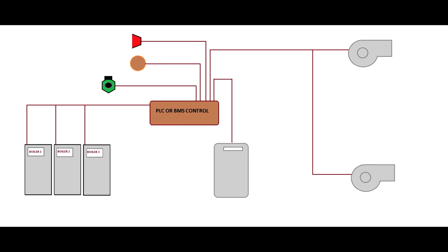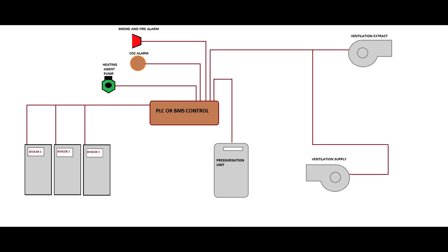So the fire alarm, the CO probe, the circulating pump, the pressurization unit, and the fans were sending inputs to the building management control, and ultimately the building management control was sending a signal to the boiler whether to run or not. So basically, the ventilation system has been interlocked with the building management control and not with the boilers directly. Or they should be both. If you interlock the BMS, the building management control, you should interlock each boiler through a group of relays, because safety takes over the control.